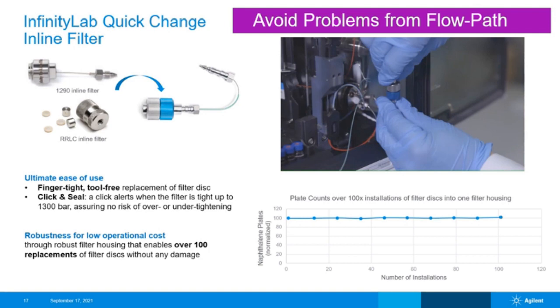Besides, since the torque to tighten the filter housing is so small, the filter housing won't be damaged at all after over 100 replacements of filter discs. As shown on the chart at bottom right, the plate count of chromatographic peaks stays stable over more than 100 installations of filter discs into one filter housing.